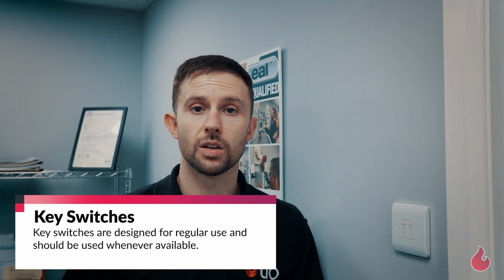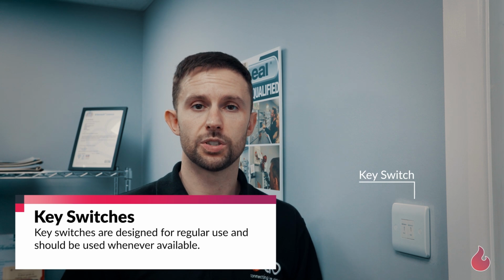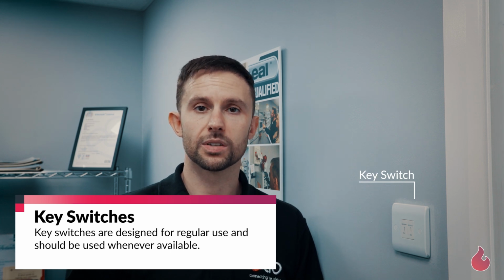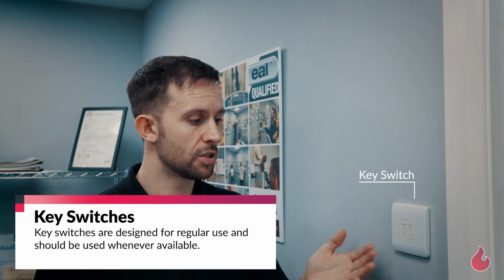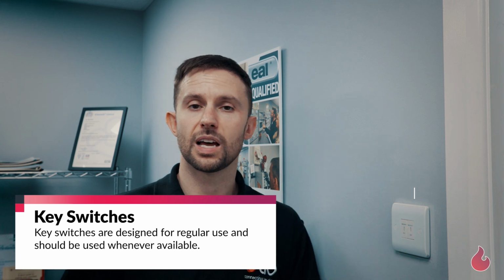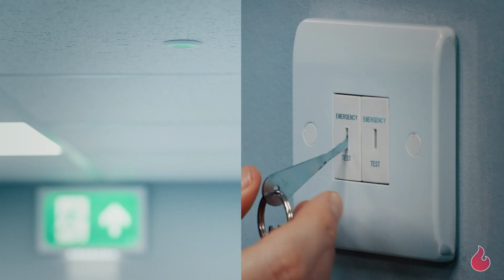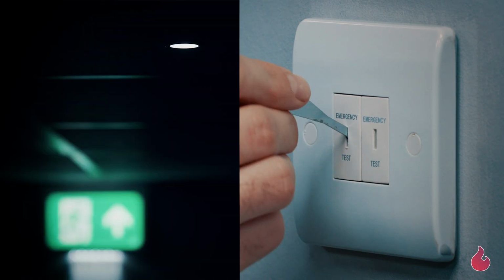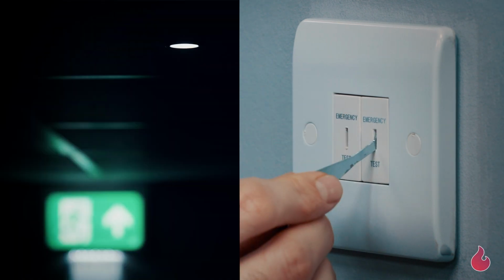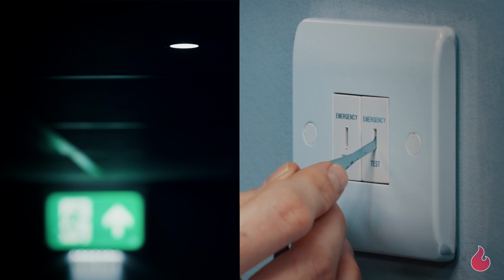The other way to test your emergency lights is via emergency lighting key switches. In most new builds or modern day builds, they'll have emergency lighting key switches that look like this. The first step is to switch off the lights in the room using the lighting switches. Second step is using your emergency lighting test key switches. Insert the key into the switch, and depending on the installation, you switch up or switch down, and this will then activate your emergency lights.